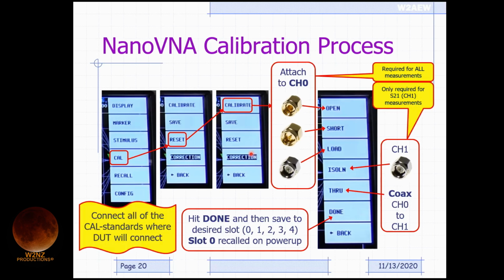I'm calibrating, do I put these little things on the pigtail that's already attached? Well, it really depends on how you're connecting to your device. So if you're measuring an antenna, for example, and you're going to connect that right to the connector on the VNA, you can connect these right there. If you're connecting through a pigtail or something like that, that's not going to be the same place where you're actually using it. Ideally you'd apply those as close as possible to whatever device, wherever you want to make those measurements. In some cases, it doesn't really matter, right?